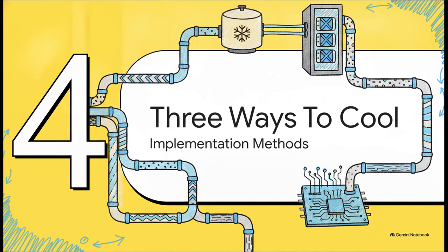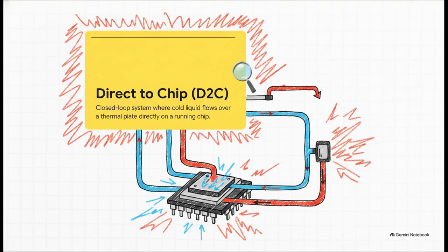Moving right along to Section 4, 3 ways to cool. So how do you actually implement this? The first way is direct-to-chip, or D2C. This is a closed-loop system. Instead of blowing air, you use a thermal transfer material to attach a cold plate directly onto the top of the running CPU or GPU. Then, a small pump circulates cold liquid right over that plate at the precise source of the heat. The liquid absorbs the heat instantly and carries it away.